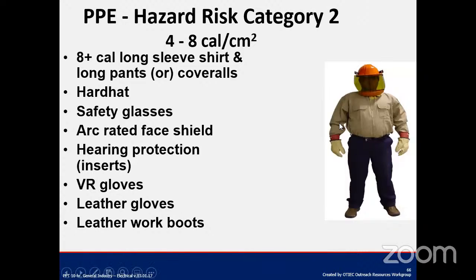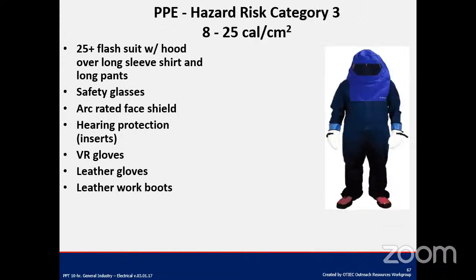Next case, the arc-rated face shield. Your uniform also changes slightly, and it's going to withstand 8 calorie plus. At this level you can see there is a separate setup, no face shield now. He is wearing a long sleeve pant with the flash suit. This is a complete flash suit.